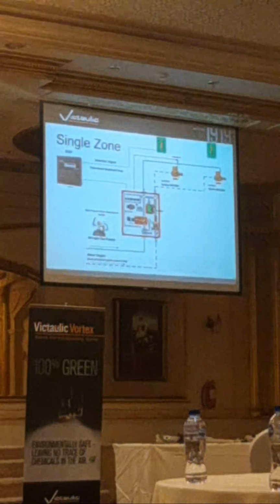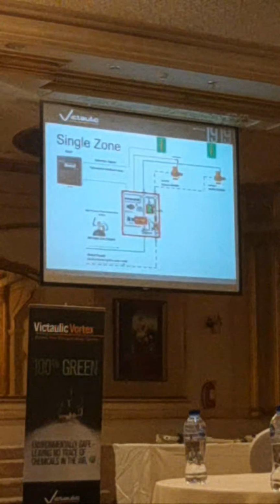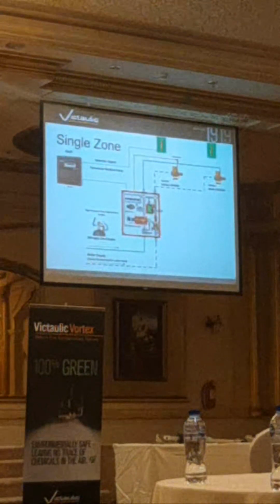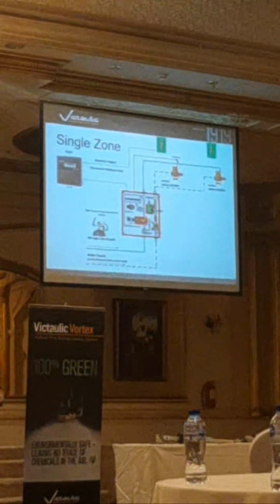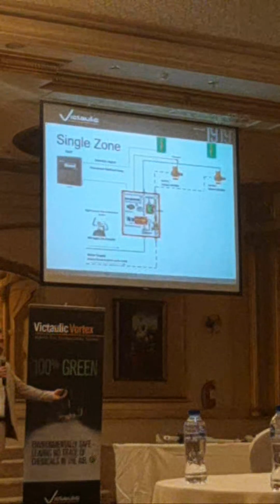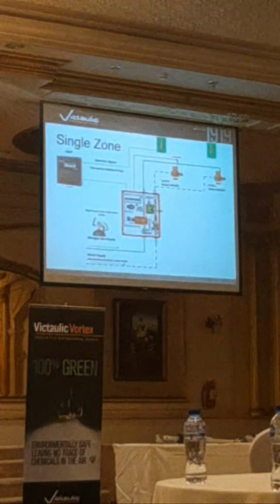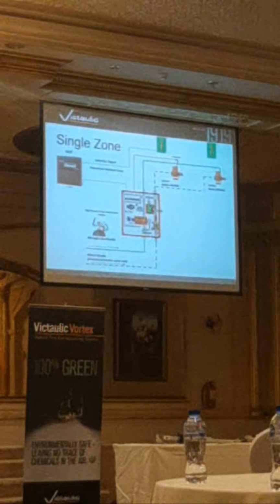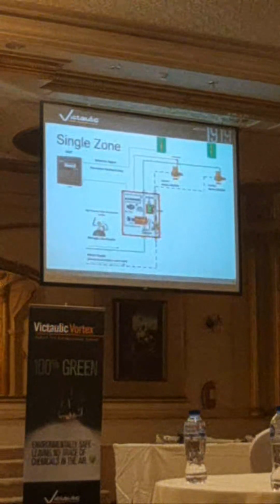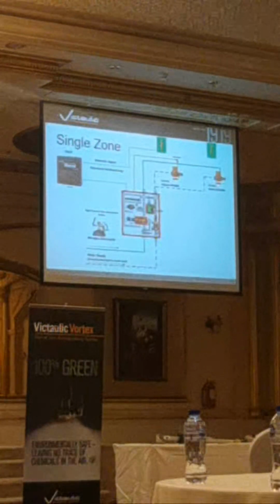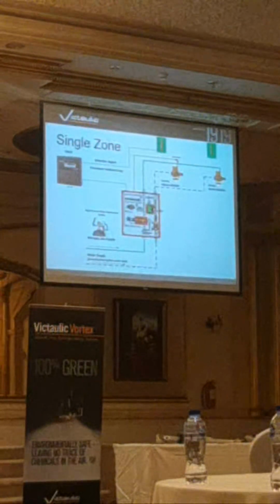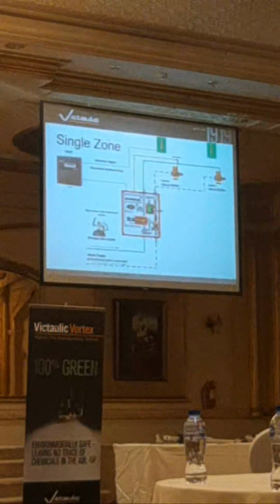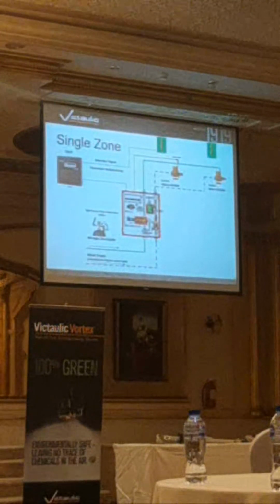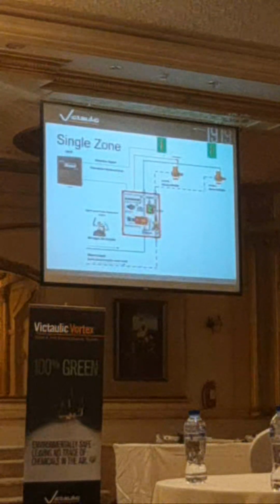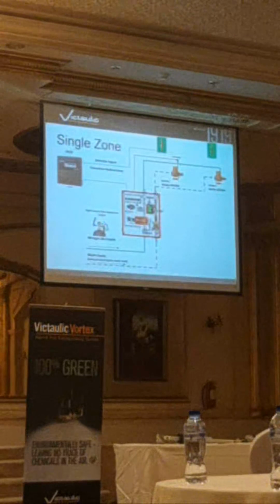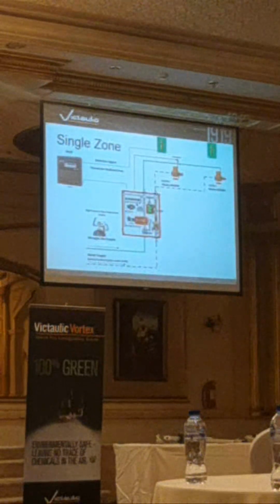Victaulic provides the system; however, we work together with training partners who are needed according to requirements, and those will be certified by Victaulic once they show that certification. They enter into a partnership with us. We train them completely and keep them up to date on the latest updates of the system, but they know more than we do when it comes to detection, because we're not experts in detection or fire alarm panels. Depending on the application, you can use any sort of detection you want - the only thing we need is a 24-volt releasing signal. Once we have that, our solenoids do the job, cylinders activate, and we perform a discharge.